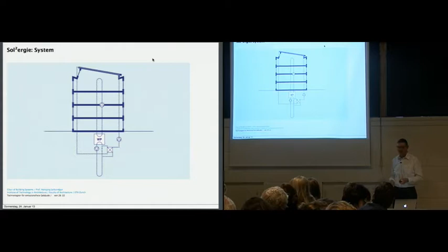So what happens in summer: we produce heat that cannot be used, and we transport it through these two circuits into the soil, depositing it where it was taken out six months ago. So we replace the heat we took out in winter. That's a question of sustainability. If you take something out of a system, you have to replace it at minimum in the same quality. We do it with higher quality because we have to accept quality losses, not energy losses, over those six months.